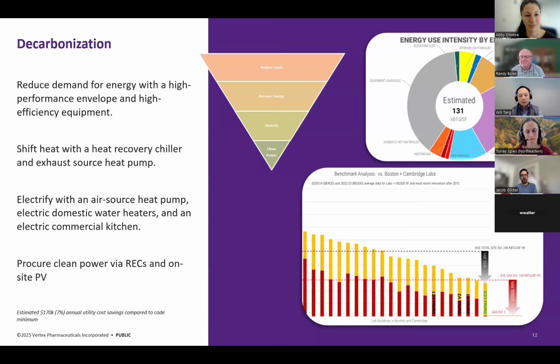This is where the reverse triangle comes in. We're reducing our load. The first thing is reducing our outdoor air heating demand. We recover the heat exhausting through the exhaust unit, because a laboratory building has to run 100% outside air. We're also decoupling our ventilation from our thermal load, providing ventilation to meet the air change demand for a particular lab, then using fan coil or active chilled beam within the space to recirculate air within that lab so there's no cross contamination, and to provide thermal comfort. That alone reduces the amount of outside air needed.